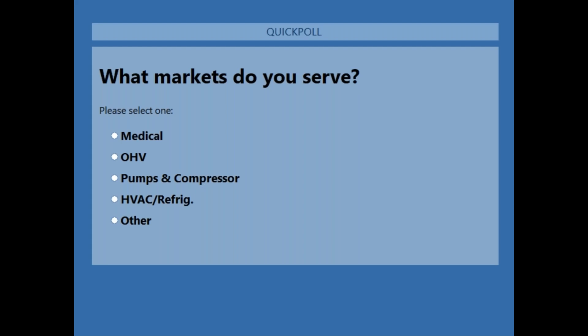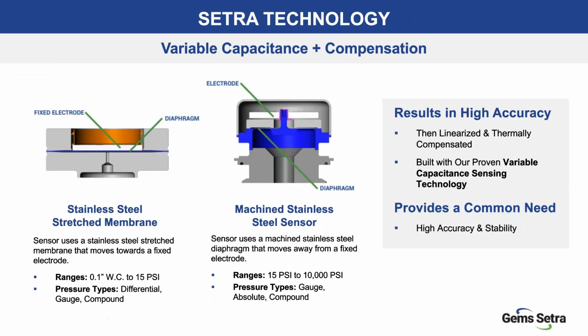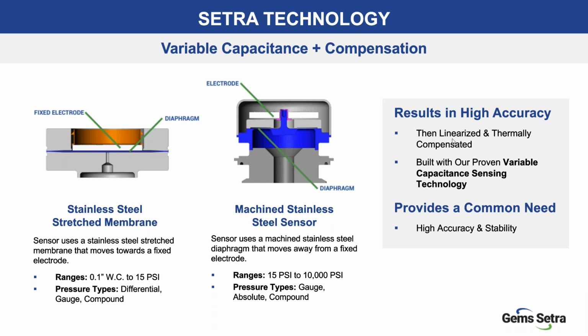To meet these needs, we start with our proven variable capacitance products for very low to high pressure needs. This, coupled with our unique compensation process, allows us to provide a high accuracy solution to serve the markets. Pressure ranges as low as 0.1 inch of water column up to 10,000 PSI ensure that we're able to meet those needs. These result in a linearized and thermally compensated sensor that provides that common need of high accuracy and stability.